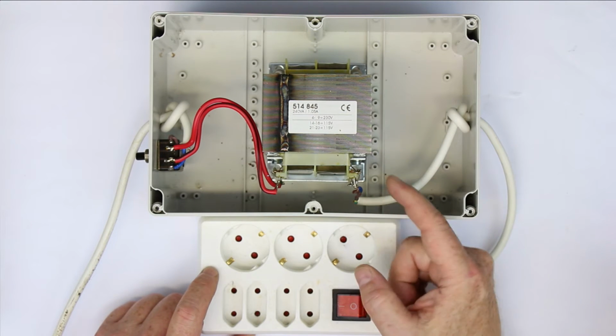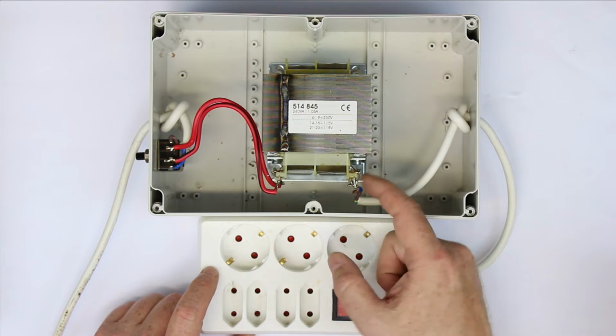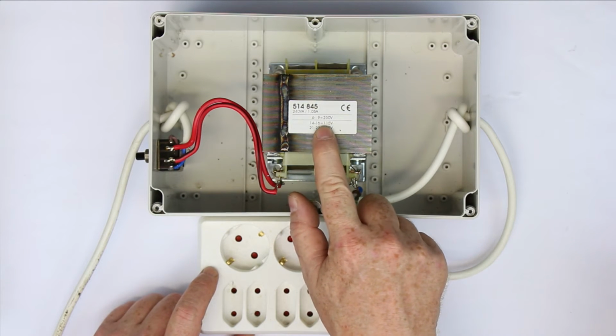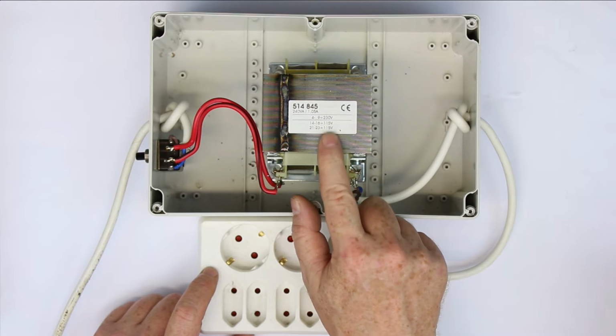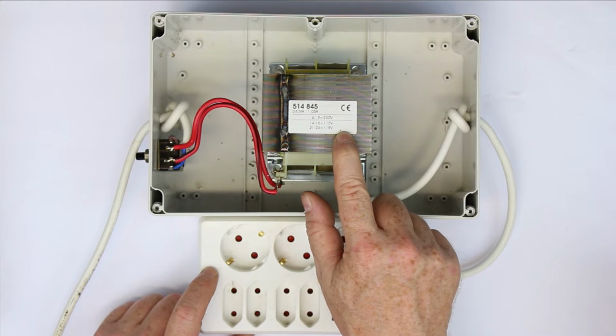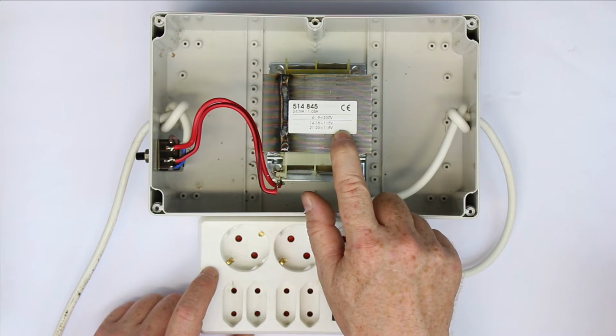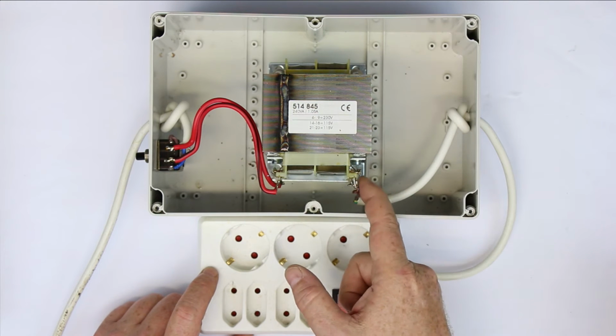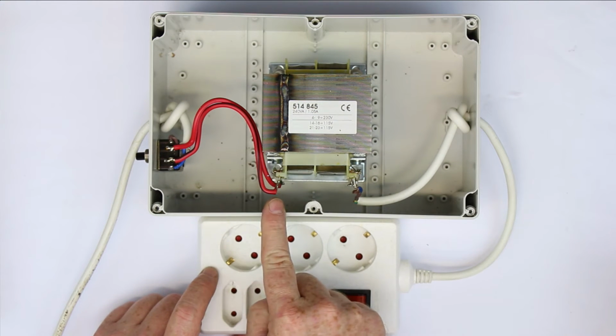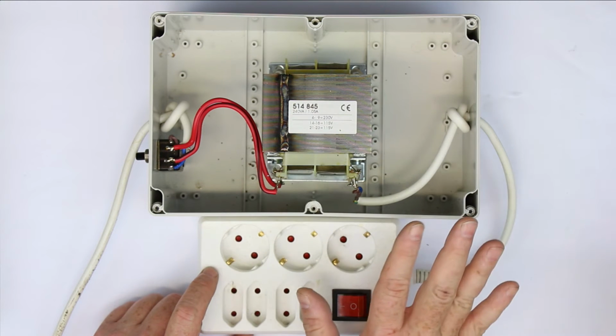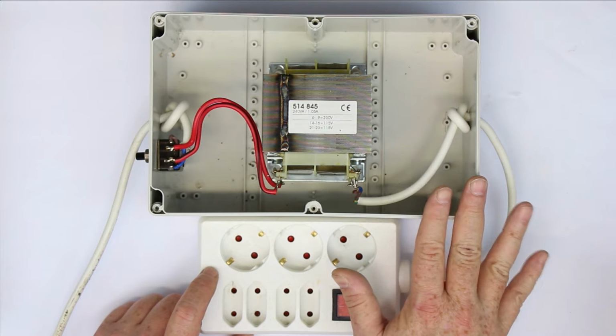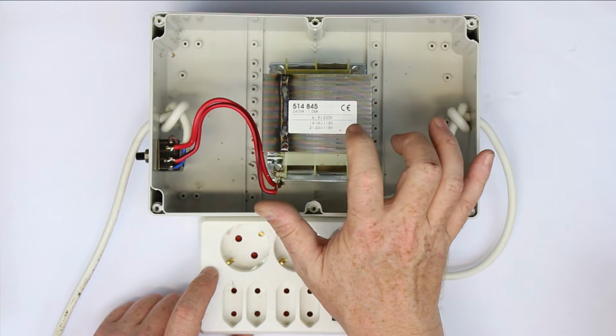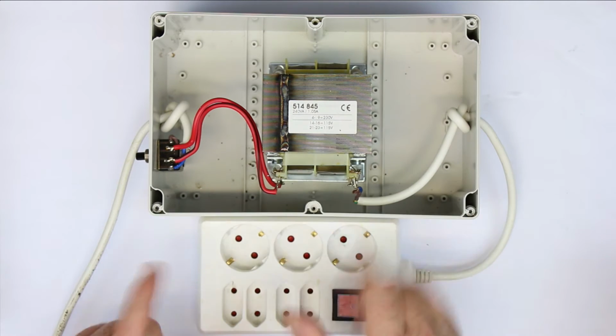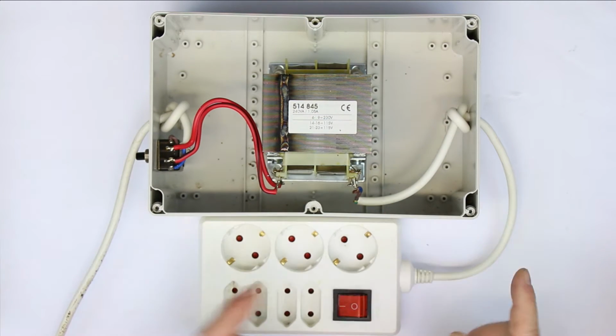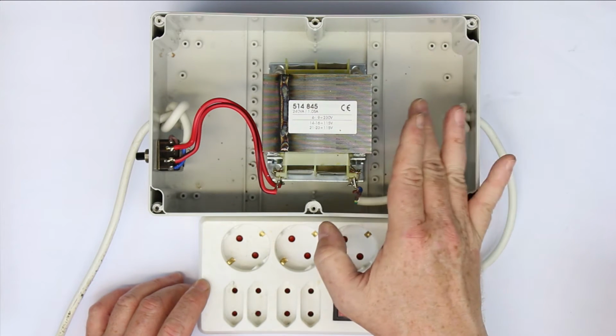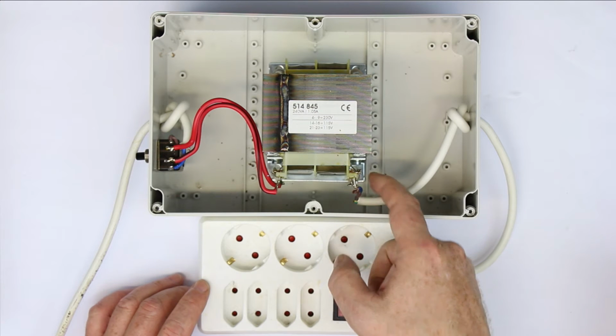There's also a nice feature here: on the primary side we have 230 volt input, and we have two secondary windings, both 115 volts. If you parallel the secondary windings, you also have an adapter for getting 115 volt devices working at 230 volt mains, or the other way around if you interchange input and output. That's a secondary use, because most isolation transformers have two separate windings.